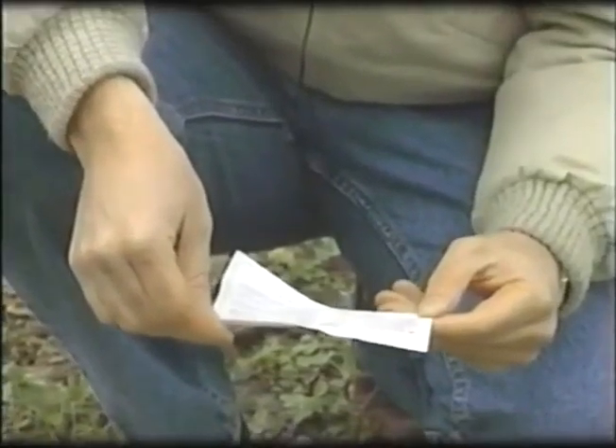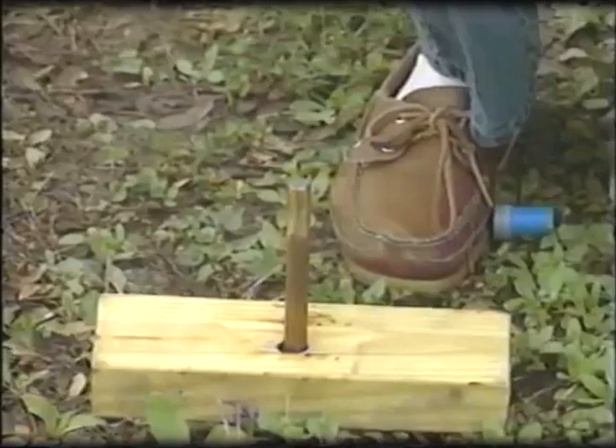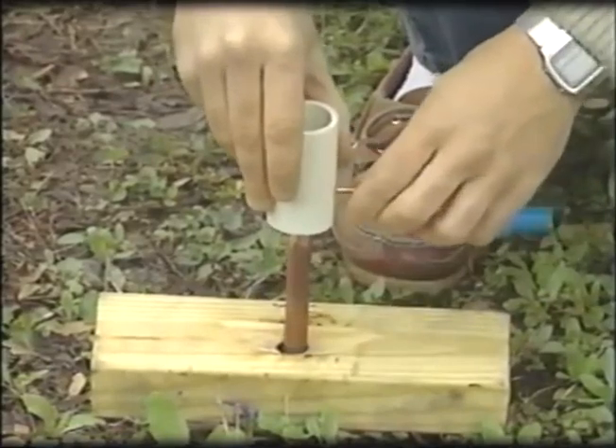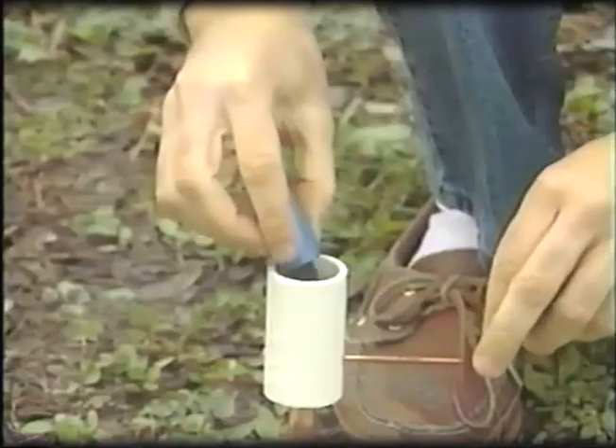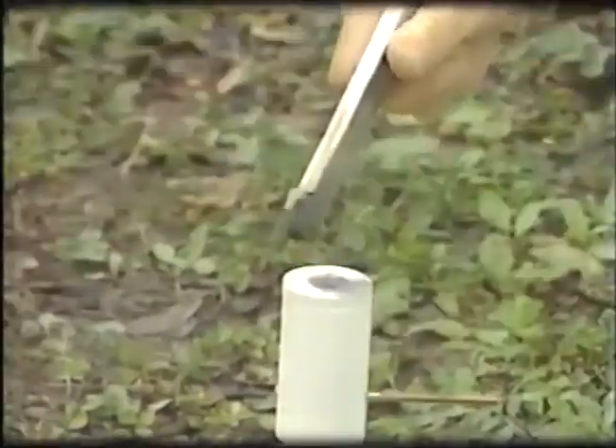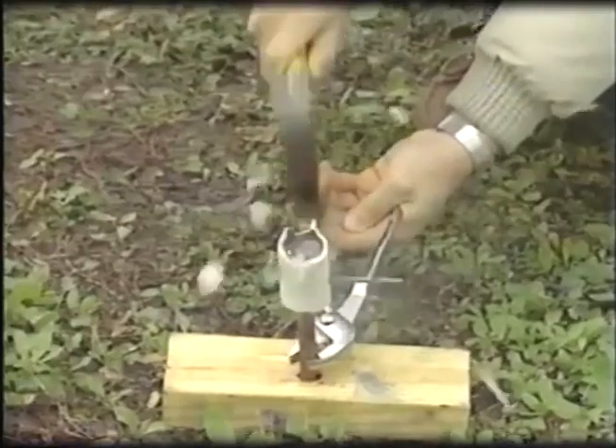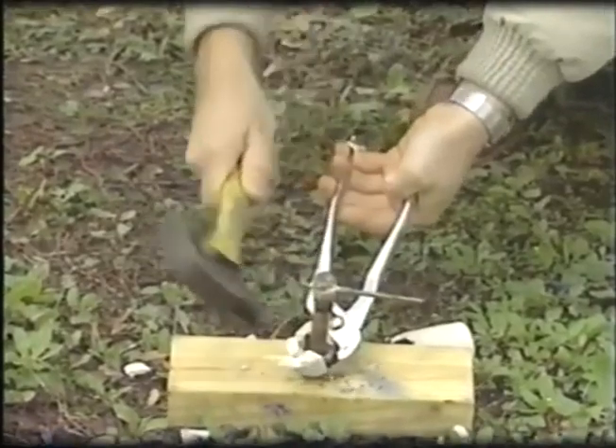First, carefully read the manufacturer's instructions and safety precautions. Next, clean the top of the rod and the end of the wire. Then, slide the exothermic weld crucible over the end of the rod and slide the wire and related parts in place. Drop the disc in, pour the weld material in, place the cap on the crucible, and then pour the igniting material onto the cap. Ignite the weld material using a flint striker and you are done. You can break the crucible and check the weld after about 30 seconds, but be careful, it's very hot.